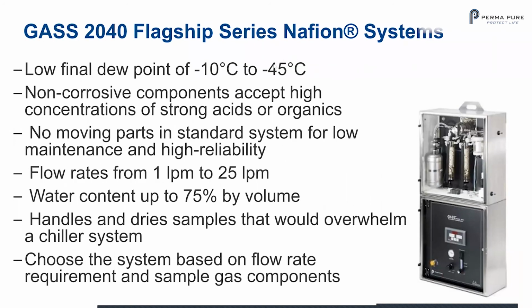The GASS 2040 flagship series really does the job with a low final dew point of -10 to really up to -45 degrees C. Non-corrosive components accept high concentrations of strong acids or organics. No moving parts in standard system for low maintenance and high reliability. Flow rates from 1 to 25 liters per minute. Water contents up to 75% by volume. Handles and dries samples that would otherwise overwhelm a chiller-based system. And choose the system based on flow rate requirement and sample gas components.